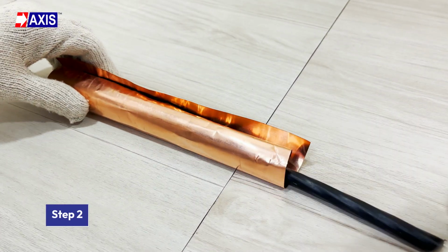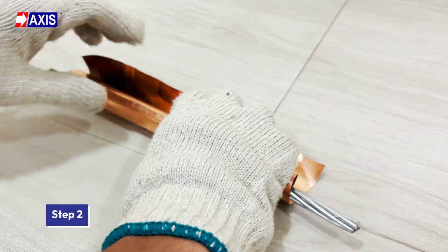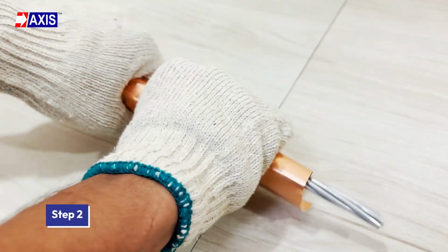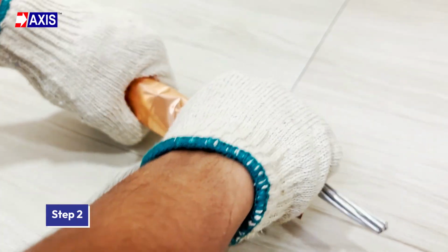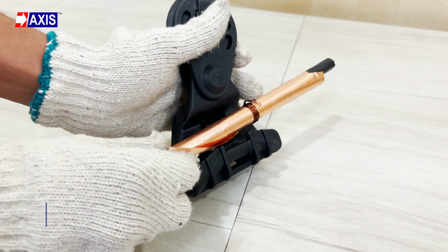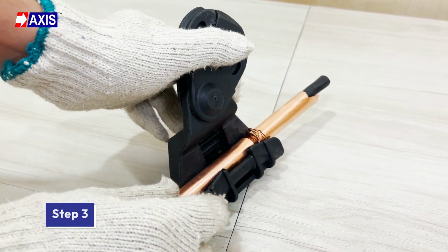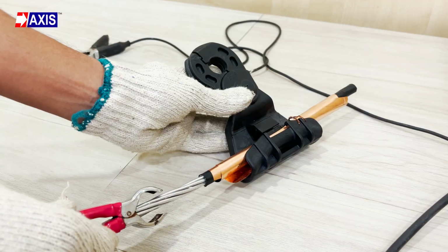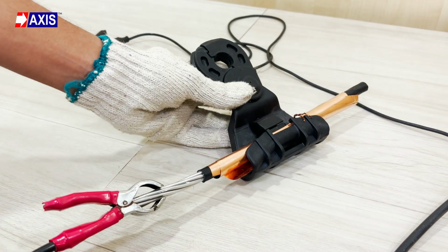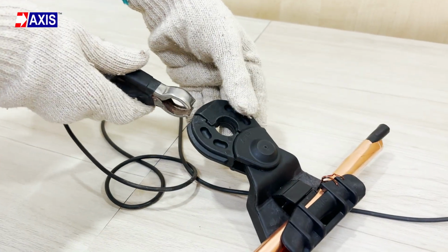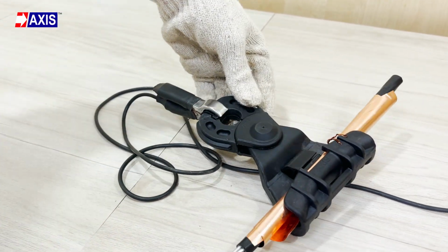Step 2. Wrap a conductive foil or wire around the insulated neutral messenger of the maximum cross-section designed for the clamp. Step 3. Insert the assembly into the clamp. Connect the conductive foil to the high voltage terminal. Earth the conductive parts of the clamp or its metallic fixing point.